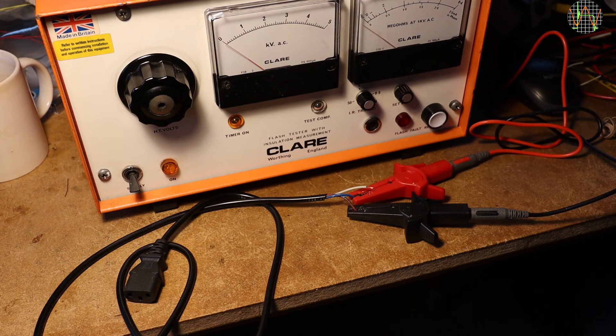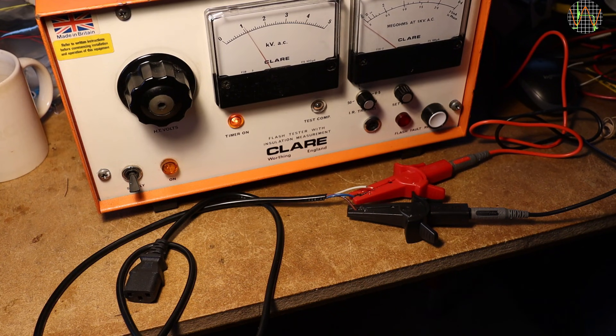Now that I have a flash tester, let's use it. The tester is set to 1000V which is applied for 10 seconds. If there is a flashover, an ear-splitting buzzer will sound. But nothing, which confirms the successful 1000V test I just did with the Extech.